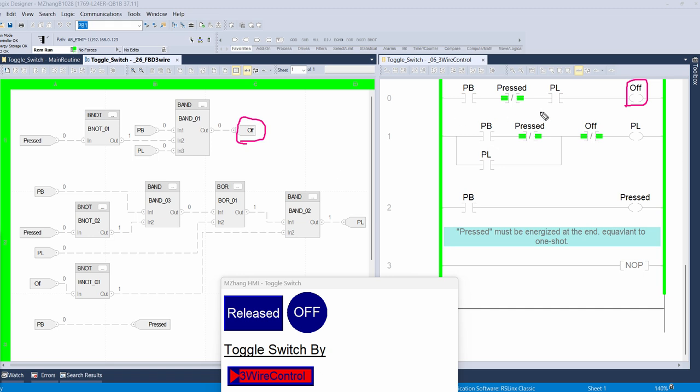All right, so to energize the off in the ladder diagram, you can see here we have 3 instructions. They are in series, right? So that's the AND logic. So that's why you can see here, right? So that's the function we choose called BAND, Boolean AND logic, right? So it has 3 inputs, 1, 2, 3, and the first one for sure you can see here it's a PB, and that corresponds to the first instruction, right? XIC on, and then we have an XIO off with a pressed. So that really is a NOT logic before you wire into there.